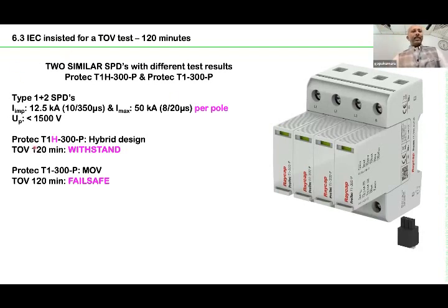Now there are two SPDs. For example, Protec T1H and the Protec T1. The difference is only that H, only one letter. So the first one is a TOV 120 minutes withstand, 440 volt withstanding SPD. The next one is fail safe. Fail safe in the sense the SPD will fail. It will fail safely. It will not blast. So the cost of, for example, this fail safe, let us say it is 10 rupees. The cost of the other one, withstand, maybe it's about 12 rupees. You know, the price will be a little bit higher. So you have to consider those things.